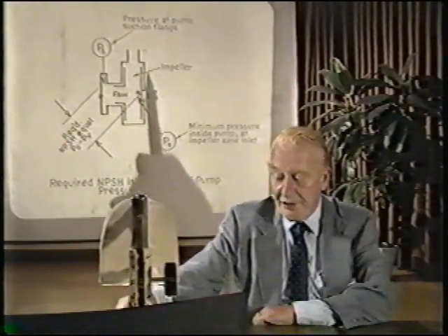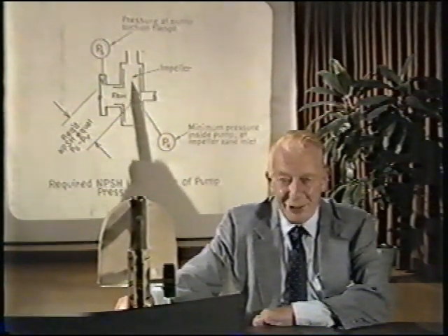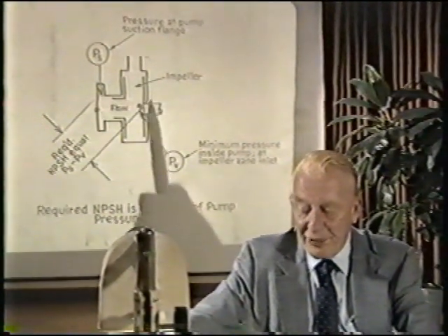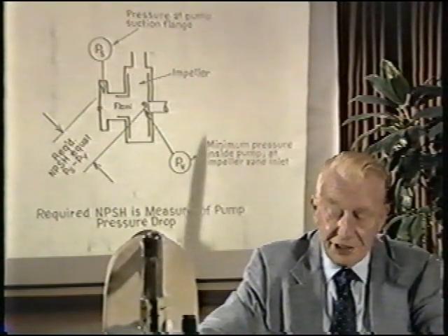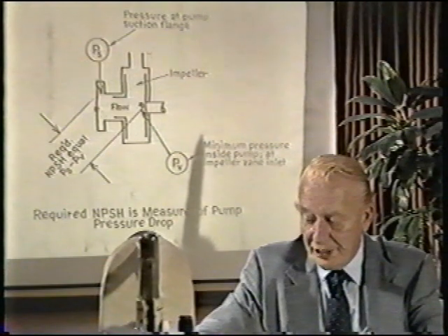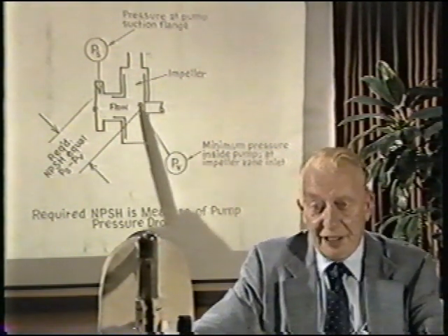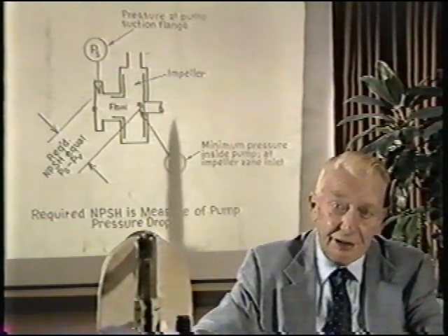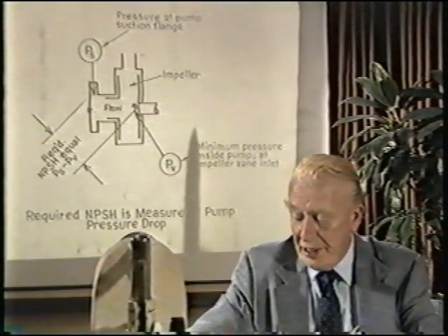The fact of cavitation will shake and rattle the pump impeller, can ruin pump bearings, can attack the seals in such a way as to cause a very shortened life on those seals, because the mechanical seals can be operating in such a way that the seals are running dry, leading to a very short life on the seals themselves.